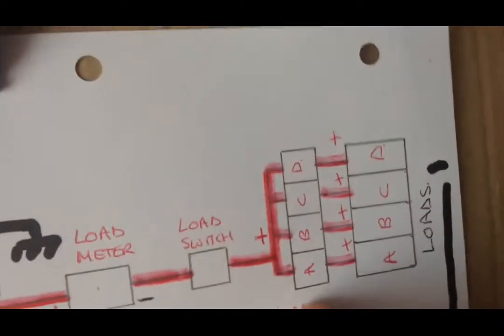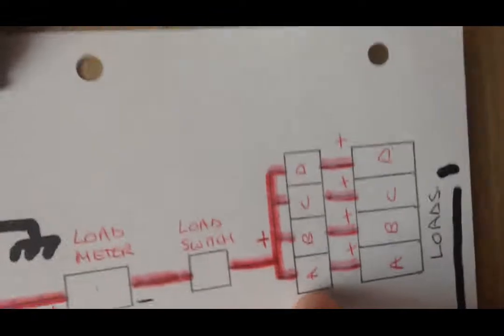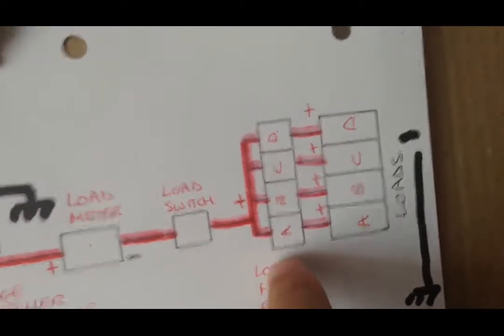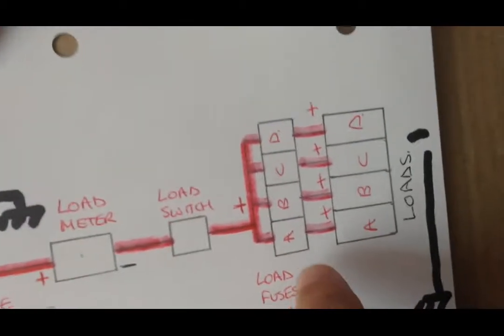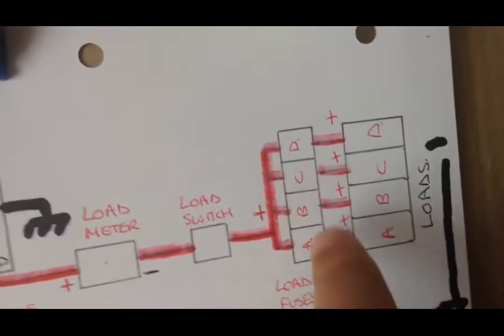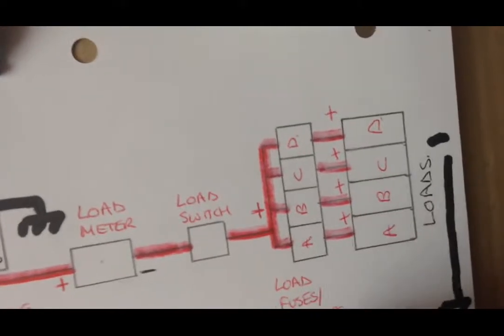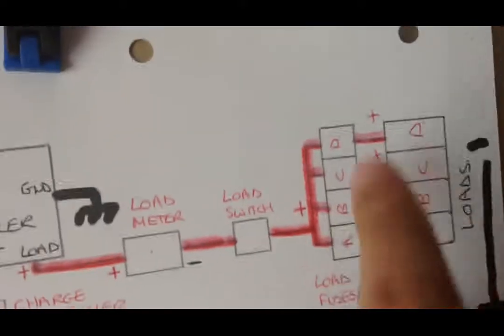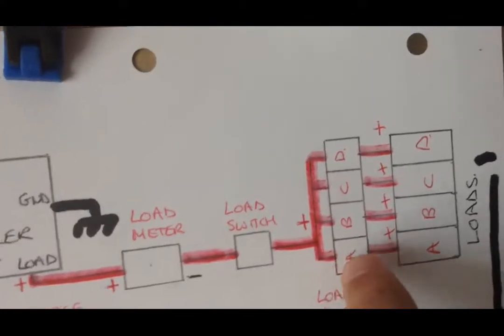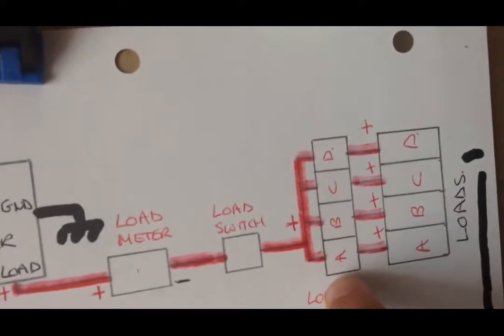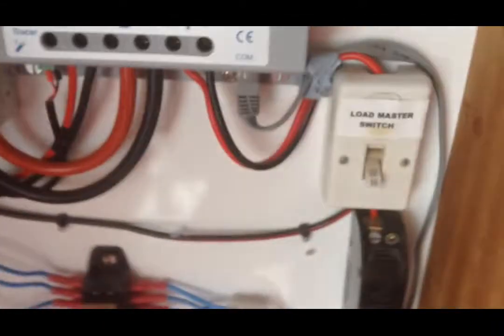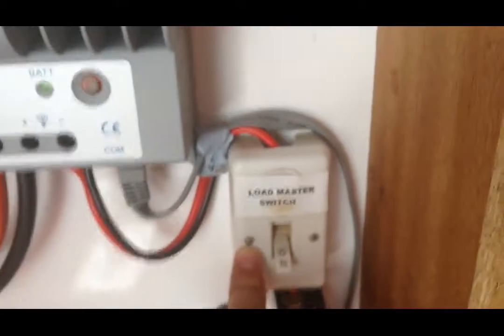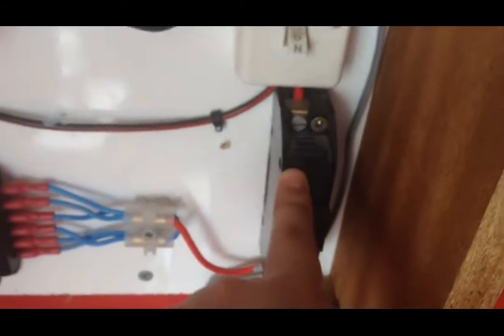After the switch comes a fuse panel. Now you can either use fuses or circuit breakers. Circuit breakers will probably be more convenient, as you can just reset them if they trip out, whereas fuses you need to replace. The only thing I can say is that fuses are a lot cheaper than circuit breakers, so that will sway your opinion on what you do here. You can either use individual fuses in the leads to your devices, or you can use a fuse box. I will show you what I have. So this is my system. There's a load switch and a load breaker.